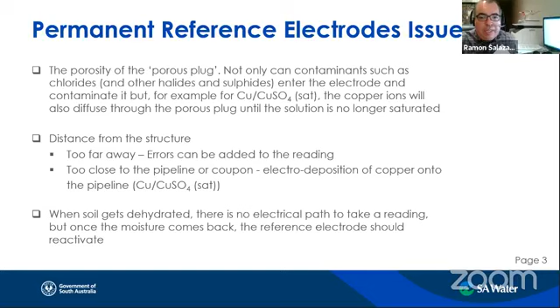The other thing that can affect a reference electrode is the distance from the structure. If it's too far away, you can have some errors added to the reading. But if it's too close to the pipeline or a coupon, you can have electrodeposition of copper onto the pipeline or the coupon, changing the metal-soil interface. The other one is when soil gets dehydrated, in case it's too dry, so there's no electrical path to take the reading. But once the moisture comes back, the reference electrode should reactivate. I would be more concerned about the third one, because we have experience in South Australia with just dry soils, and they can affect the life of the reference electrodes.